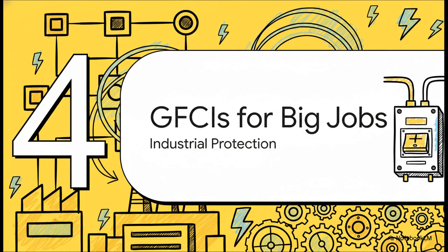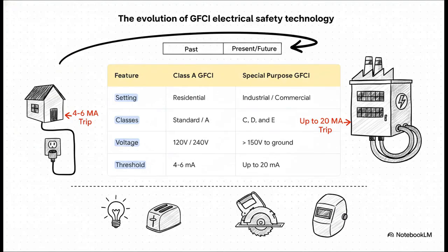This kind of smart protection isn't just for homes. When you get into bigger industrial-scale jobs with much higher electrical loads, you need a whole other class of GFCI. The standard device in your house is a Class A GFCI, but for heavy-duty stuff like industrial or big commercial buildings, there's the special purpose GFCI, or SP GFCI. The biggest difference is the trip threshold.